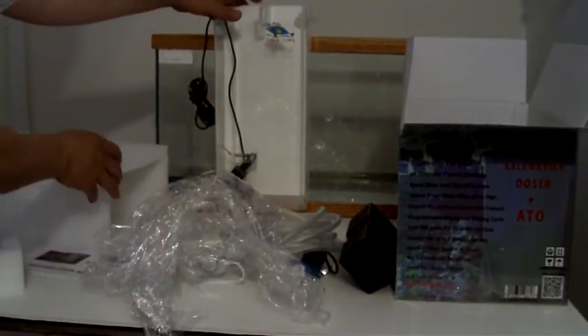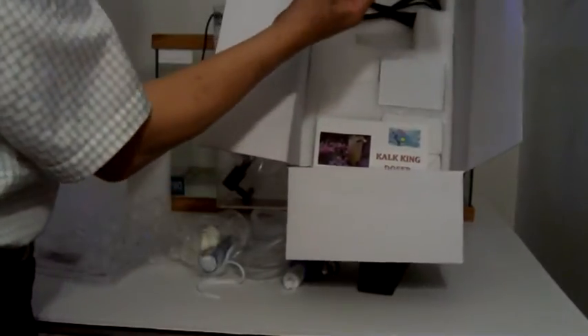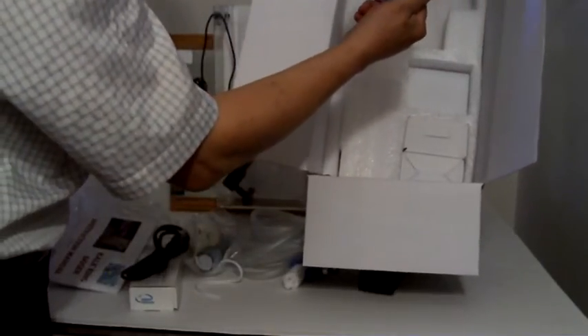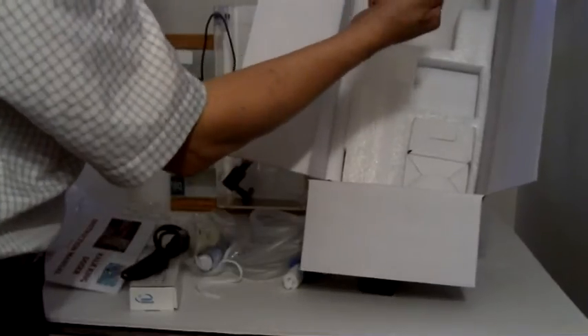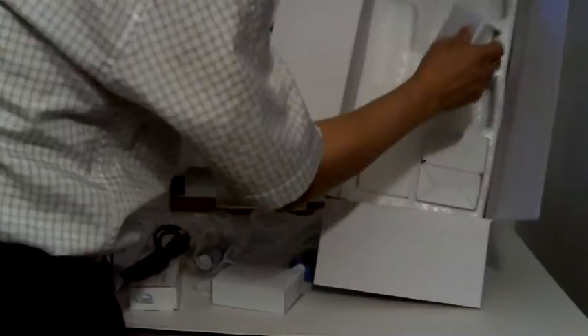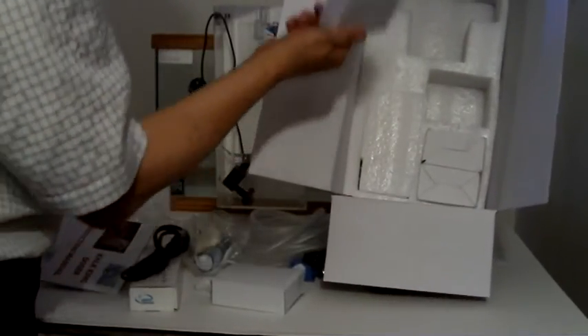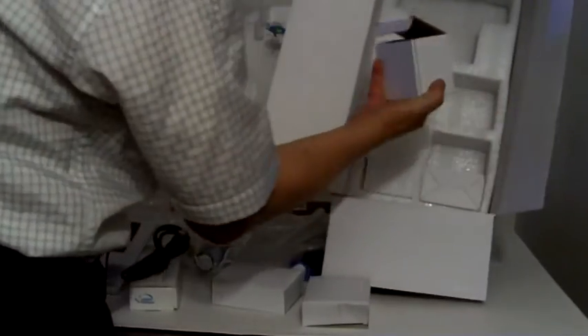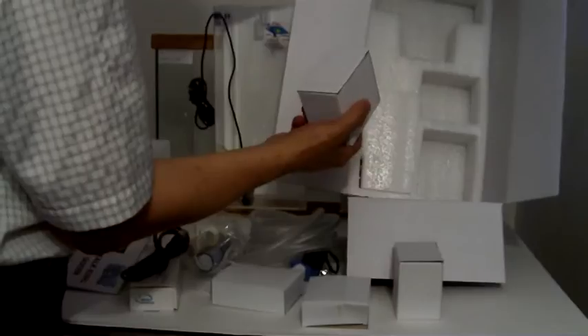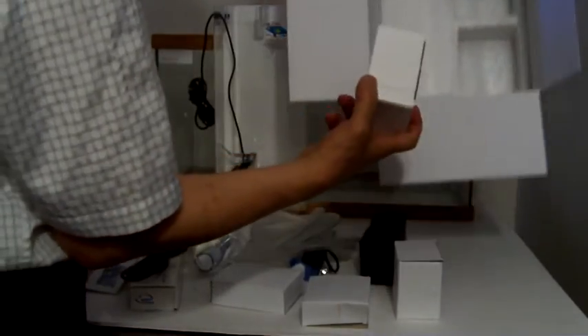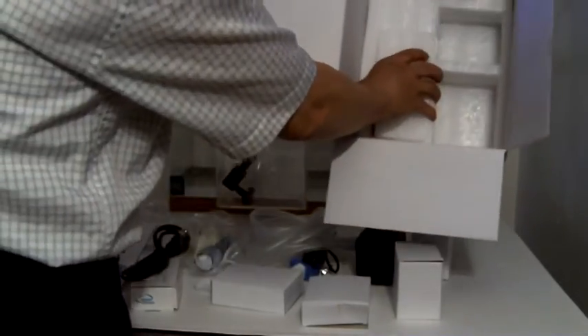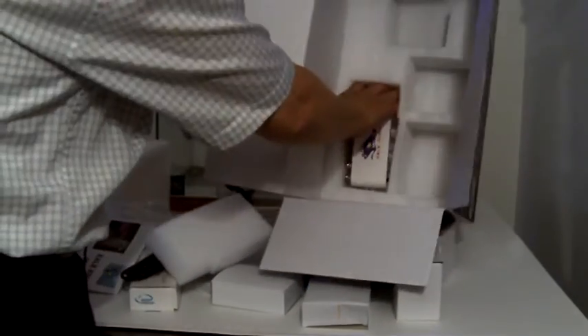Okay, so basically let me hang on here first. And on this side, you see, it's very well packaged. You have the pH meter and the cable to connect the pH meter to the computer, and also you have an AC to DC inverter for powering it. And there's another one, if you don't use the battery for the pH meter, you can also plug it in too. And there are two extra pumps here. One is the feed pump, which is feeding the reaction chamber, and the other is bypassing the reaction chamber in case your pH setting limit is over. And the last component you can see here would be the computer control unit.